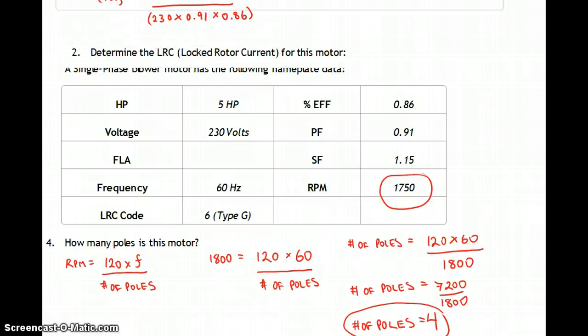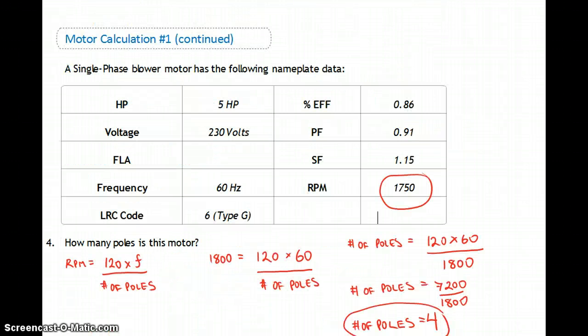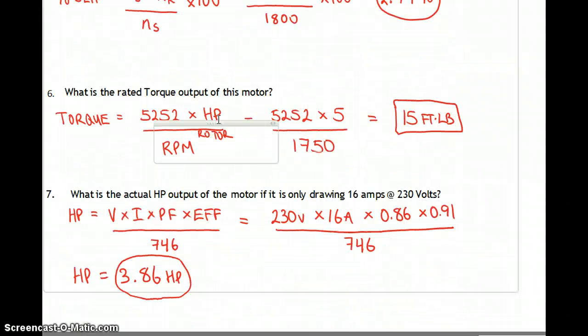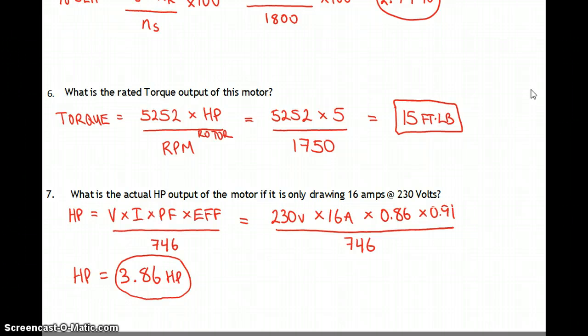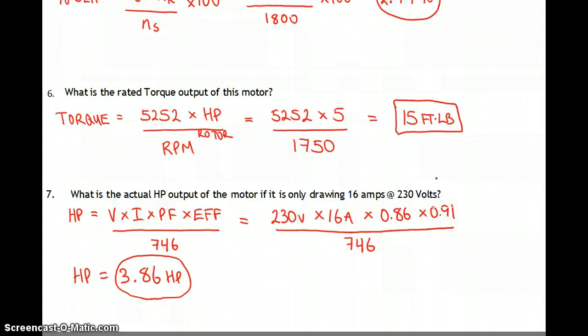Normal operating current was 20.7 amps at full load. If it's only drawing 16 amps, it's not at full load. Voltage stays at 230. So horsepower equals volts times current times power factor times efficiency over 746 — that's 230 times 16 times 0.86 times 0.91 over 746. Rather than the full 5 HP output, it's only outputting 3.86 horsepower.